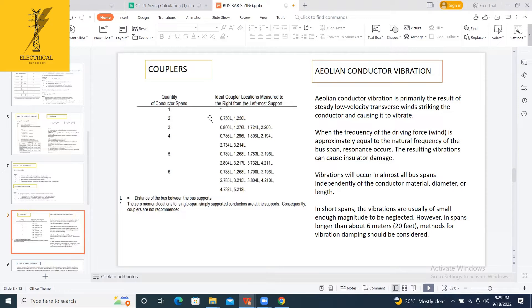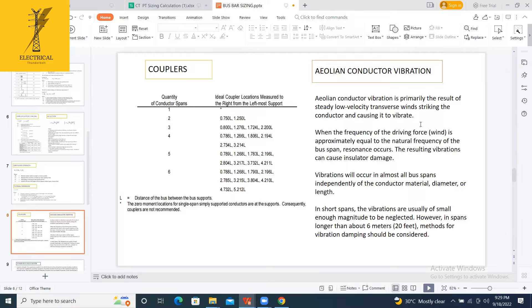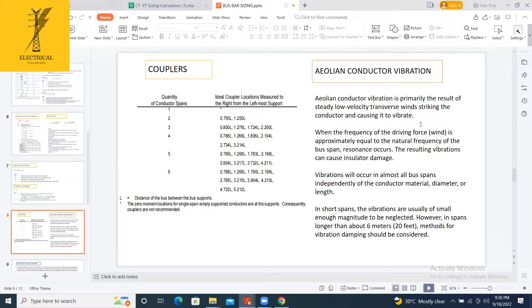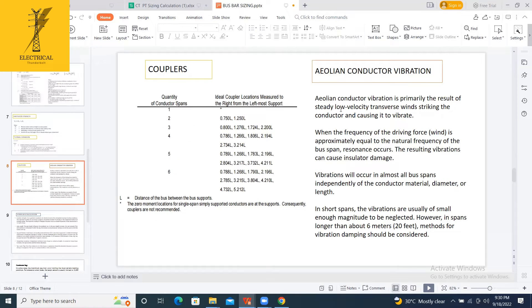Aeolian conductor vibration is primarily the result of low-velocity transverse winds striking the conductor and causing it to vibrate. When the frequency of this driving force wind is approximately equal to the natural frequency of the bus span, if both frequencies are correct, we know that resonance occurs. This may result in conductor damage. Vibrations will occur in most bus spans, independently of the conductor material, diameter or length. In short spans, the vibrations are usually of small enough magnitude to be neglected. However, in spans, if the span is more than 6 meters, generally vibration dampers should be considered.